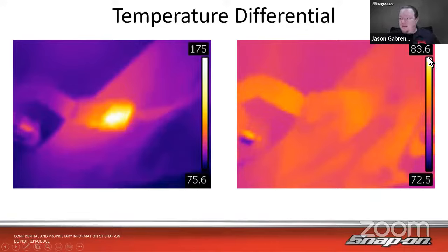So white isn't necessarily hot — white is warmer relative to the rest of the scale, it works relative to each other. So 83.6 at the top, 72.5 at the bottom, versus 175 to 75 — there's a big difference between those two temperature ranges. Just be aware, white doesn't always mean hot; it could still be 50 degrees for all you know. Always make sure you're looking at the scale on the imager.